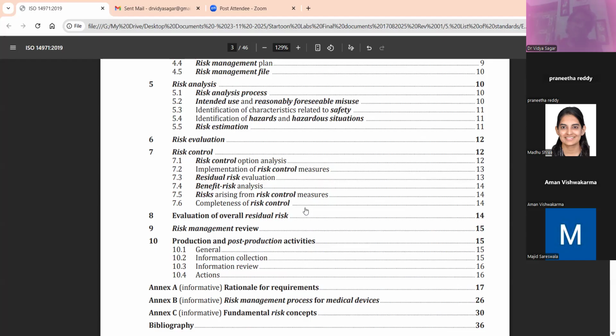So what I'm trying to say is, with PMS, you should look very carefully in the context of risk management. This will give you inputs on what new risks are encountered which you have not documented in your risk management. That you need to add. And you also understand what is the situation that caused the risk. That's why I say you need to study complaints, okay, in all dimensions. Because there you will find why that hazardous situation happened, and how the hazard converted into a harm.